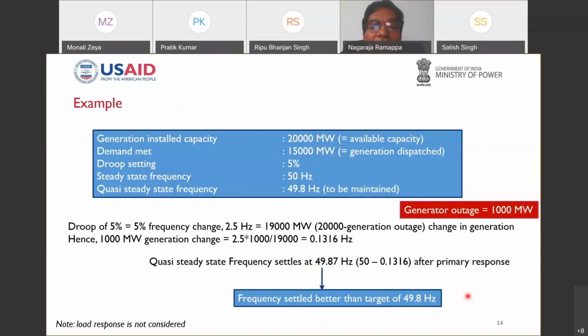Now, we need to understand how crucial our governor control is. Therefore, for a generation installed capacity of 20,000 megawatt, the primary response is very, very crucial. Therefore, we need to understand the importance of a 5% or 4% droop. 5% droop means a 5% change in the frequency changes power by 100%. Even though you are all power engineers, I just want to talk about the concept of this droop very clearly, so that we try to understand what the impact of that is.